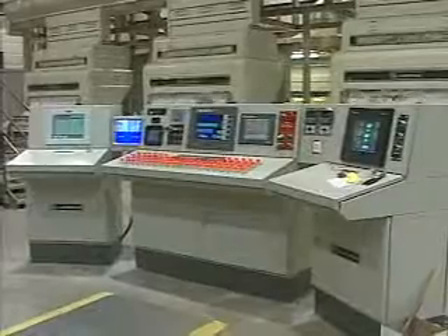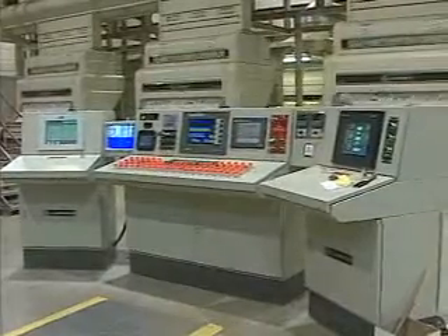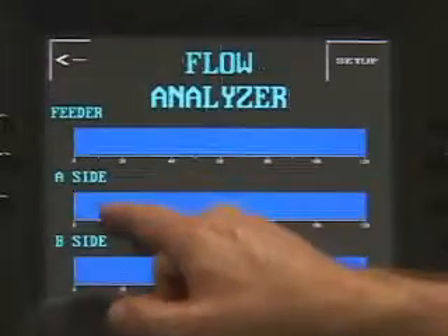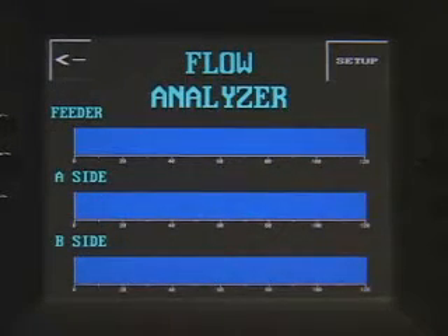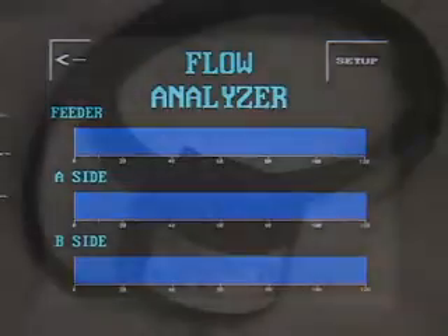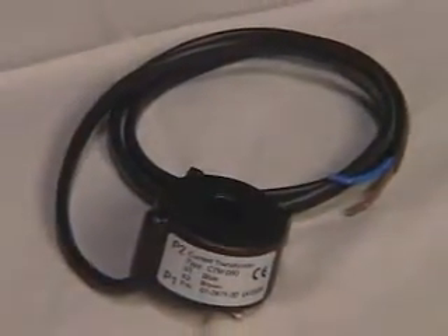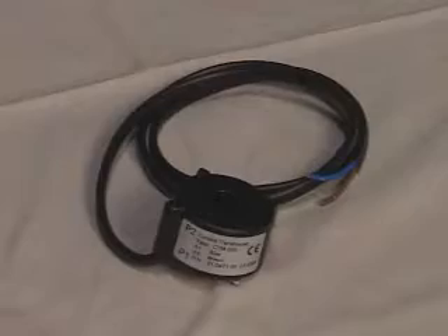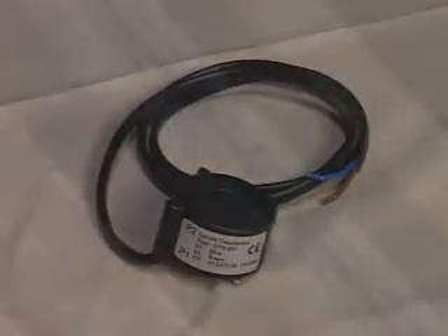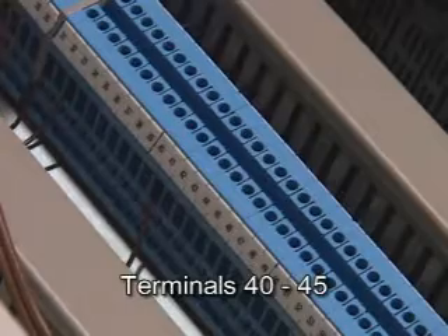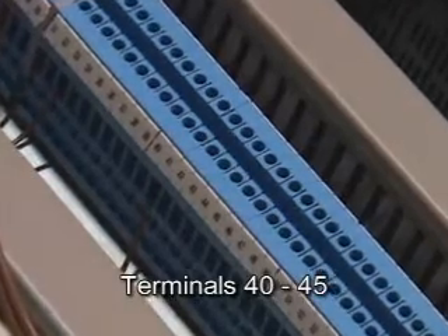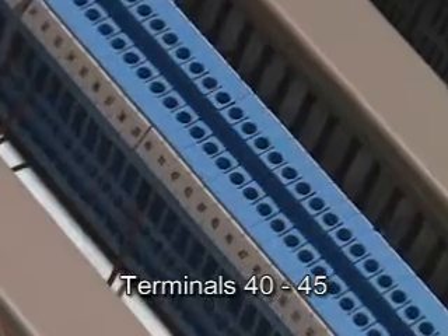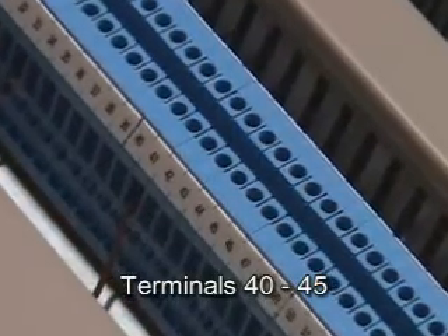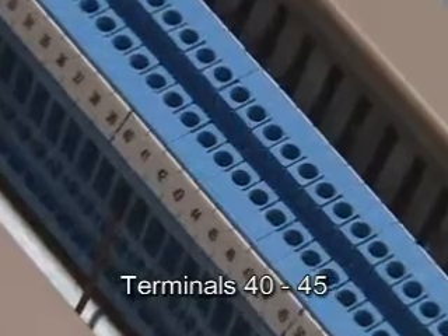If a flow analyzer is to be connected to the monitor to permit the operator to view cotton flow into the gin, note that it is important for the installing electrician to pay particular attention to the wiring of each load sensor for this function. It is phase sensitive, and putting the current sensor on the wrong phase or reversing it will make the readout impossible to use. The flow analyzer sensors connect to the monitor here. These wires carry very low voltage and are safe to handle. The sensors at the motor control center should only be connected by a qualified electrician as they carry 480 volts. See the service manual for calibration instructions for each flow analyzer sensor.